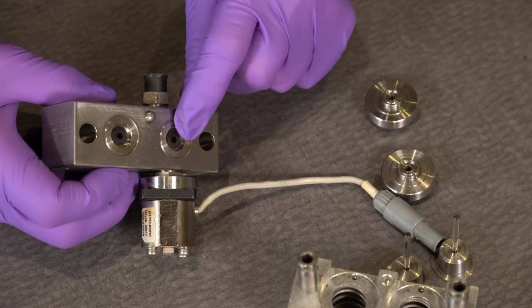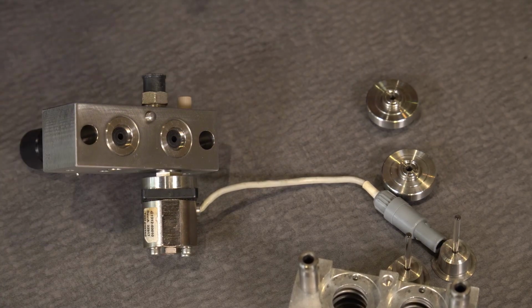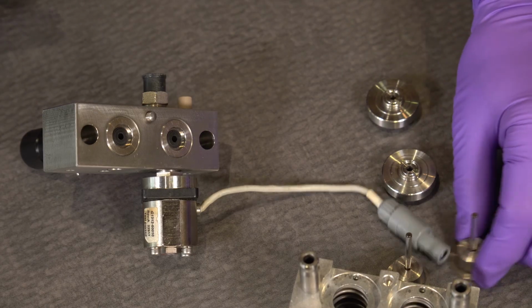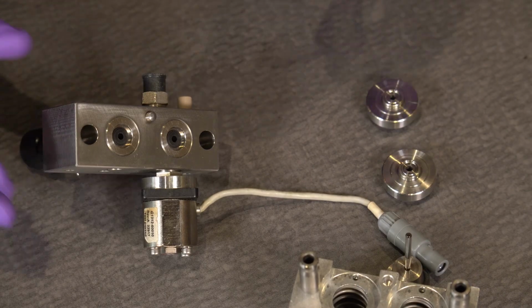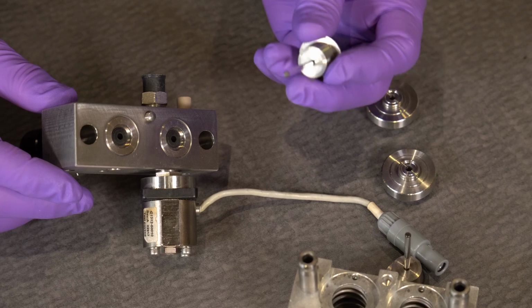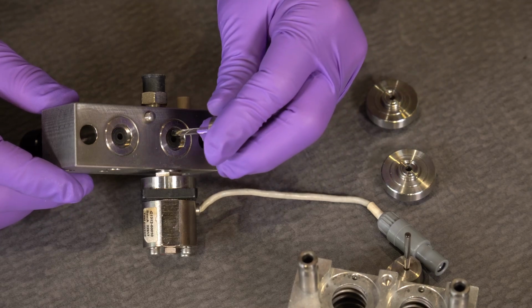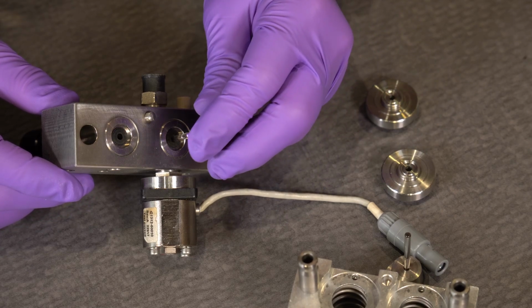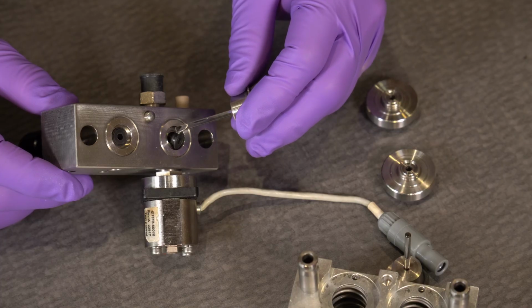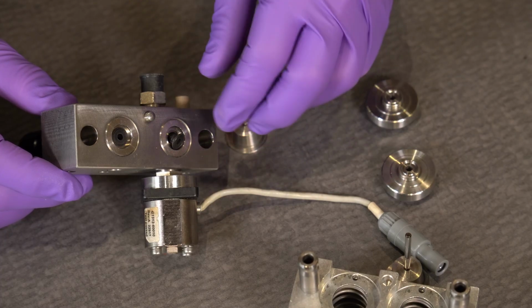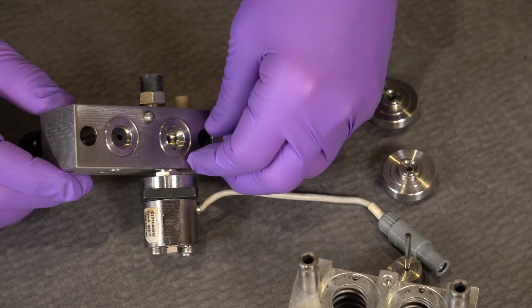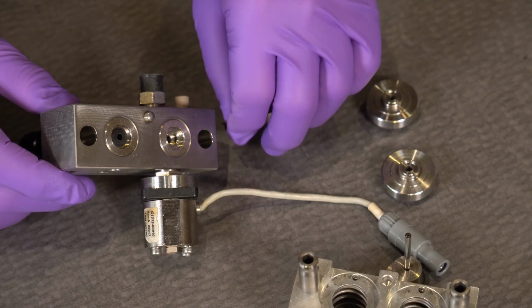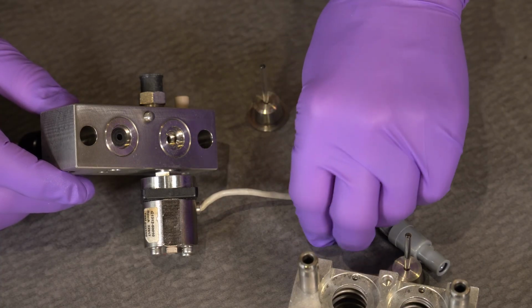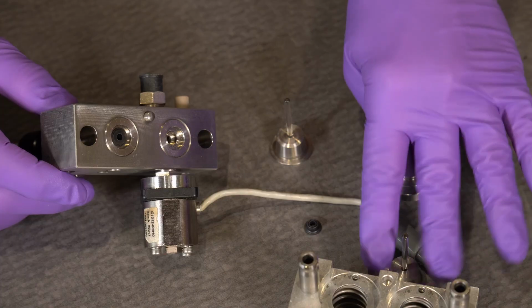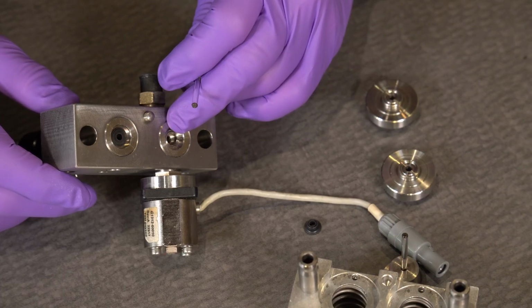So if you see those two little pieces of black plastic, those are the pump seals, and eventually they're going to wear out. So how do you remove them? There's a couple of different approaches, but my favorite approach is just to use the piston itself. You put it in just a little bit, and it's probably going in a millimeter or two, and then I simply rotate it out. So you could think about it just, I'm prying it out. Although it sounds strange to use a sapphire rod as a pry bar, you get the idea that you're not prying very hard. So that's the one pump seal.